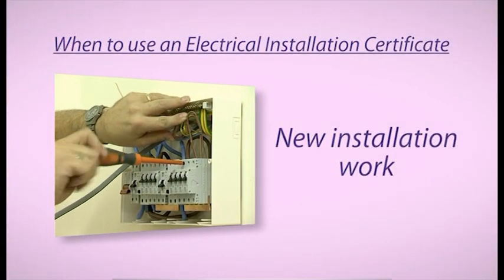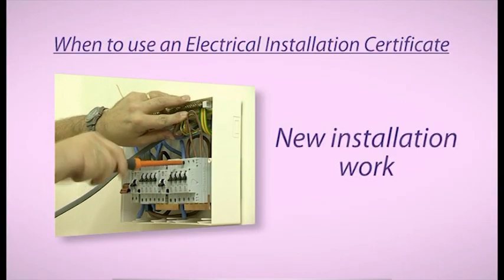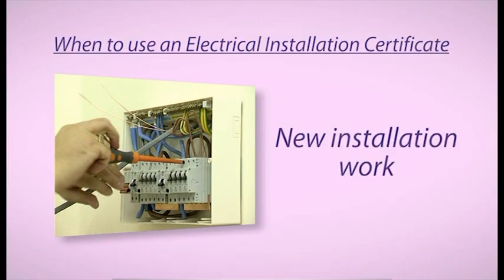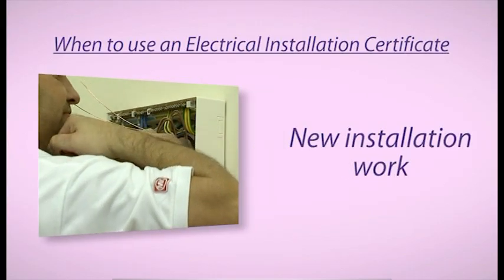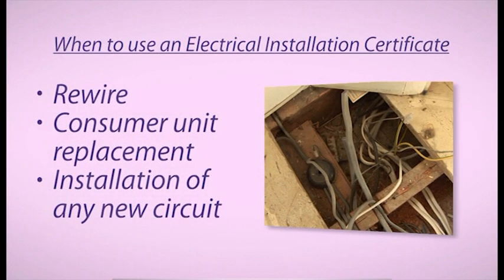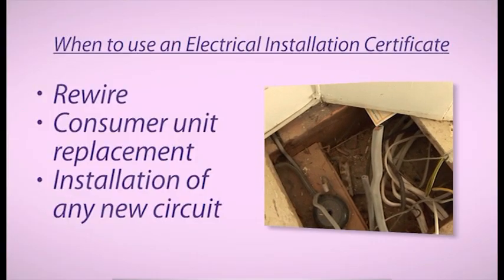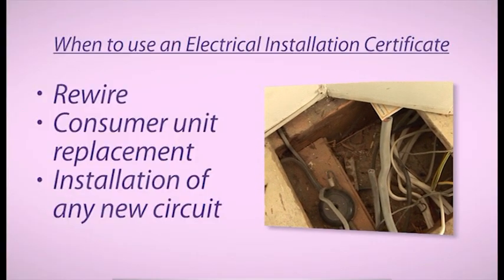That's a good question, Dave, because surprisingly the answer isn't as straightforward as you might think. Its most common use is for new installation work, for example on a new build project where the electrician will be confirming the standard of the work and the safety of the whole electrical installation. However, it could also be used for a rewire, a consumer unit replacement or the installation of any new circuit. So what Tony's saying is that although it has the word installation in the title, it doesn't always mean the whole installation.